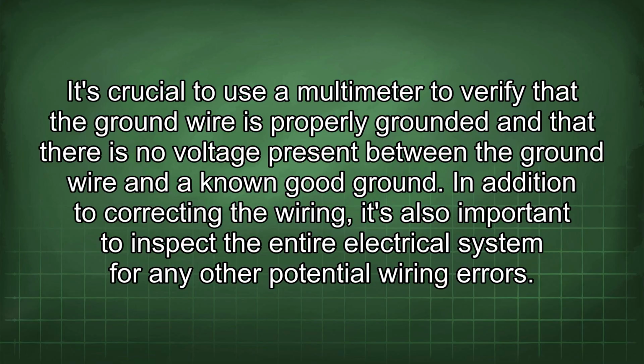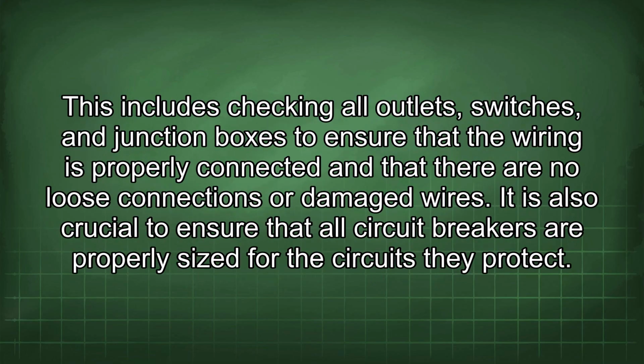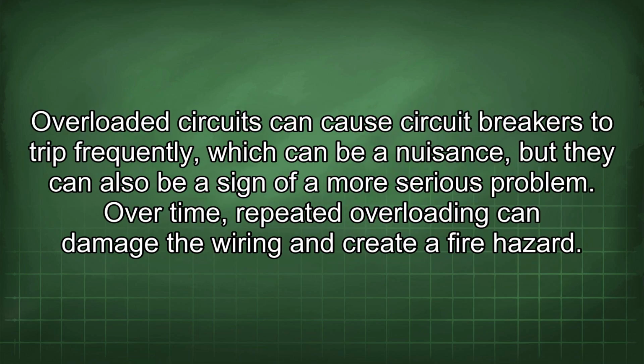In addition to correcting the wiring, it's also important to inspect the entire electrical system for any other potential wiring errors. This includes checking all outlets, switches, and junction boxes to ensure that the wiring is properly connected and that there are no loose connections or damaged wires. It is also crucial to ensure that all circuit breakers are properly sized for the circuits they protect. Overloaded circuits can cause circuit breakers to trip frequently, which can be a nuisance, but they can also be a sign of a more serious problem.